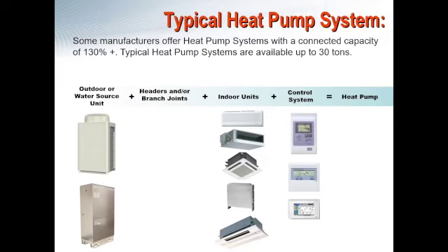We have a variety of indoor units, which we'll touch on, all the different types, later on in the presentation. But what you have to think of is that's the piece of equipment that is going to be serving each individual space or group of spaces that are all going to be connected together. The last component to the heat pump system is going to be some sort of system control. That can be either a thermostat, like you see here on the right-hand side. We have a simple thermostat up top. You move down into a little bit more of a localized controller thermostat, second down from the bottom, and then all the way on the bottom you have an image representing either your central controller or your BMS system on a larger scale commercial project.